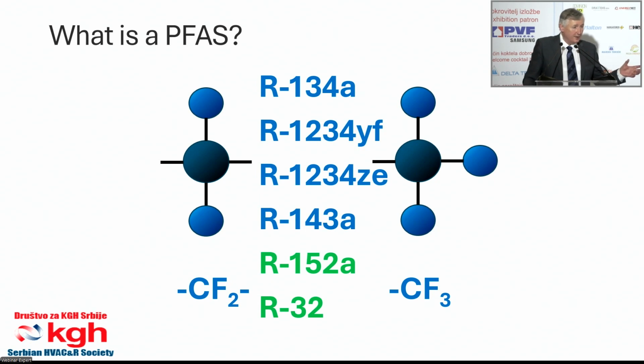Global warming potential at that time of about 140, so it just managed to slip underneath the threshold of 150 that was set in the MAC directive. And of course R32 with GWP at that time of about 675 just managed to slip underneath the 750 threshold. Interestingly, in the 6th assessment report from UNEP, the GWP of R32 is now assessed as 770, so it's actually just slipped slightly above the threshold now. And that's part of that uncertainty that I mentioned earlier.